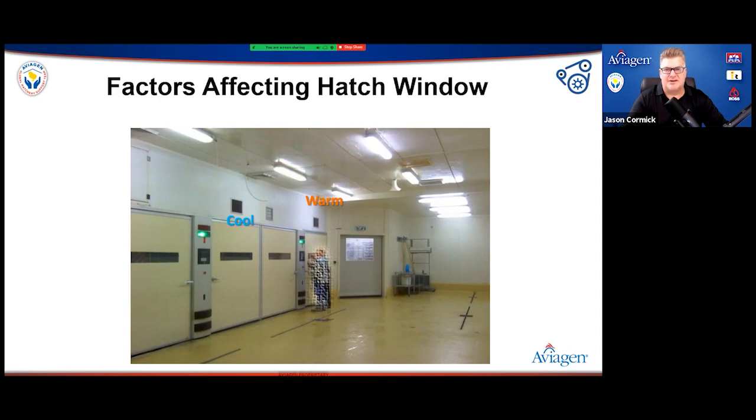So in this case, it's just easier. You see this overpressure grill. We could just switch this around here. So not a big deal, but something you need to be aware of. Make sure that all the machines are getting the same temperature air as well, if you're going to run on the same profile, because you could have tweaked the profile to allow it to vent more.